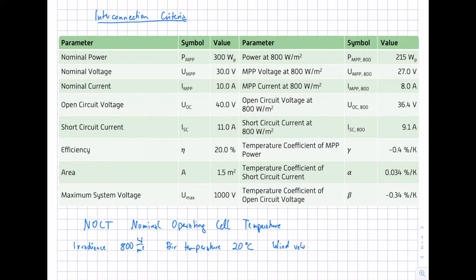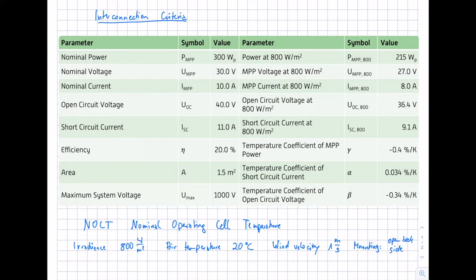NOCT conditions also include a wind velocity of 1 meter per second — which is not considered under STC — and an open backside mounting of the module. This open backside mounting means that wind can cool the backside of the modules and thus the cells. Under these typical nominal conditions, we get different values for power and voltage: the drop in irradiance reduces current, and the different temperature from STC gives different voltage and power values.